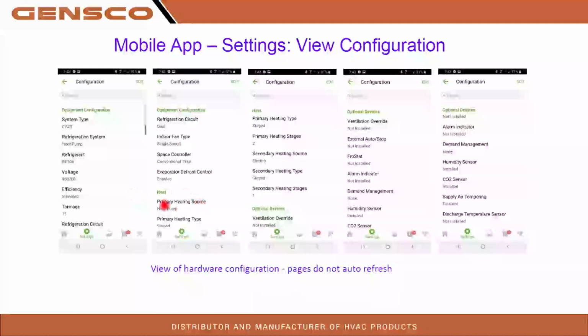We're scrolling down. You've got your primary heating type. If you have heat strip or gas heat, how many stages? Do you have ventilation override? It's possible that you do. This is a big one. Everybody thinks that if you have the third-party smoke detector in the duct, that we keep it, right? So we're doing a retrofit. We set the new rooftop unit on. That old ductwork smoke detector is still in there. Let's reuse it. We do not enable this.